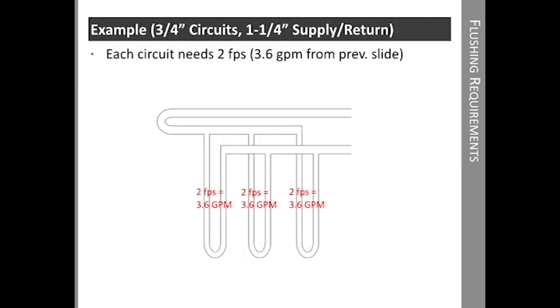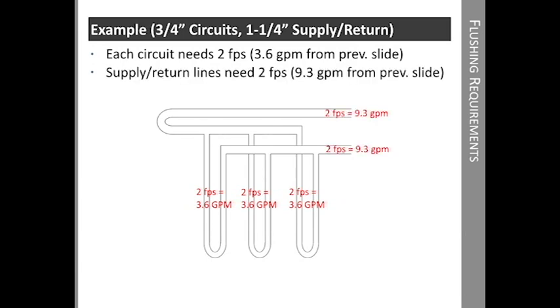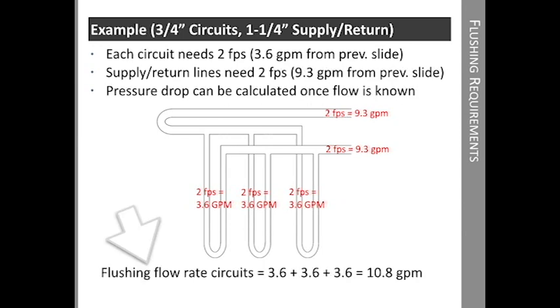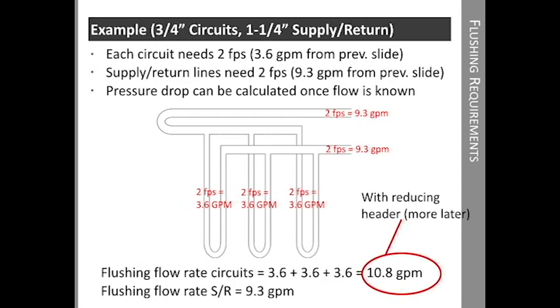Let's take a look at an example with a three circuit loop. Each circuit is piped in parallel. From the previous slide, we need 3.6 gallons per minute in each circuit. The inch and a quarter supply return lines need 9.3 gallons per minute to achieve 2 feet per second. Then we can compare flow rates to the circuits and the supply and return lines. In this case, we need 10.8 GPM to get 2 feet per second in all three circuits. Since the flow rate required for the circuits is higher than the flow rate required for the supply and return lines, the flushing flow rate is 10.8 GPM. This assumes a reducing header, which we'll talk about later.